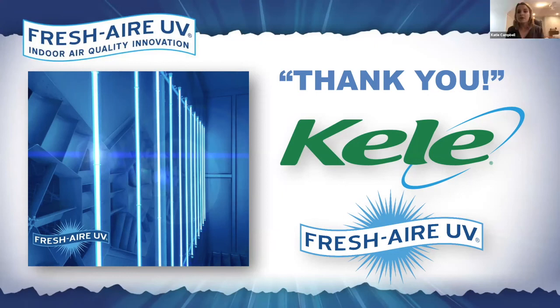Gotcha. The next one's from John. And I'm assuming, John, this is in reference to the life of the lamp. So is that 24/7 operation for 1 and 2 year lamps? Yes. So the lamps are rated in hours. So 8,000 hours for 1 year, 16,000 hours for 2 years. So it would be a 2 year continual operation. If for whatever reason the lamp is cycled or the lamp is off for 6 months of the year, then you would get four years from the lamp. So there's no shelf life on the lamp. It's not going to go bad. But certainly when we rate a lamp, it's on when it's energized.